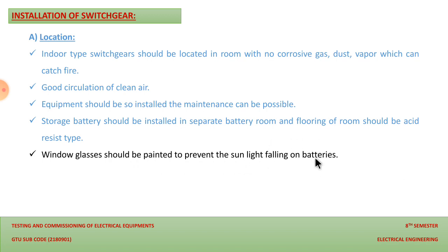So the battery room must be protected from sunlight and other contaminated air and vapor. We should keep that in mind while installing the battery in the battery room. The window glasses should be painted so that sunlight cannot easily enter the room, and from that we can protect our battery for long-lasting operation. Then an exhaust fan should be installed so that we can exhaust the unwanted air from the room where we have installed our switchgear.